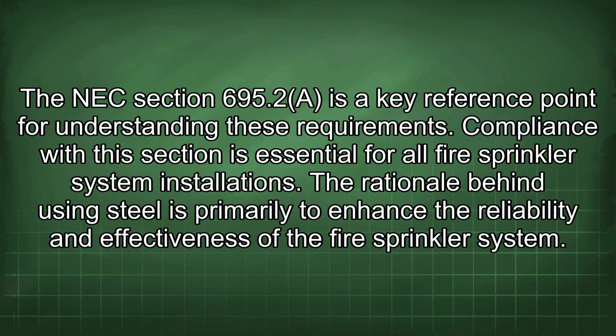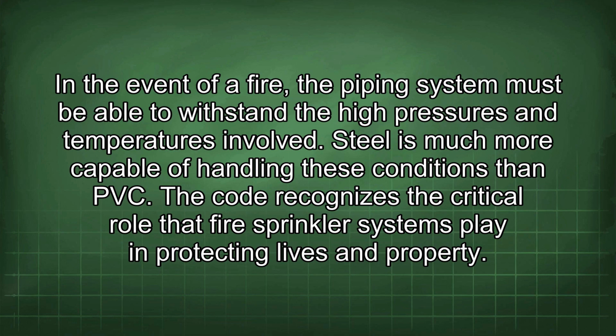The NEC Section 695.2 is a key reference point for understanding these requirements. Compliance with this section is essential for all fire sprinkler system installations. The rationale behind using steel is primarily to enhance the reliability and effectiveness of the fire sprinkler system. In the event of a fire, the piping system must be able to withstand the high pressures and temperatures involved. Steel is much more capable of handling these conditions than PVC.